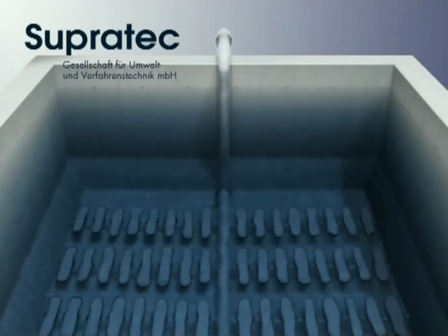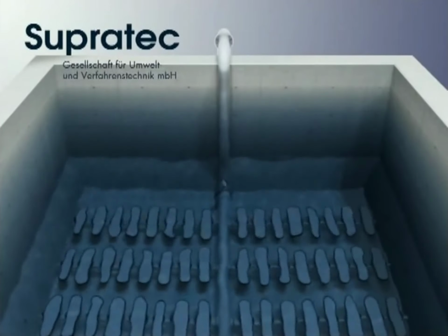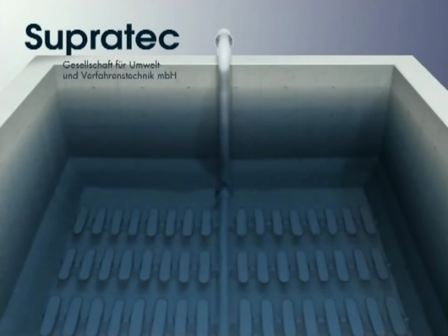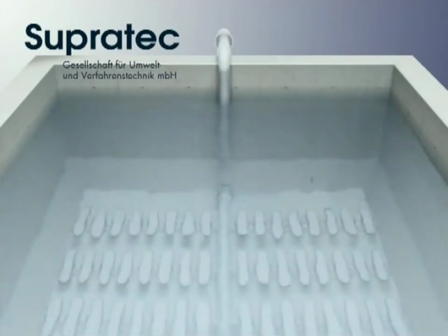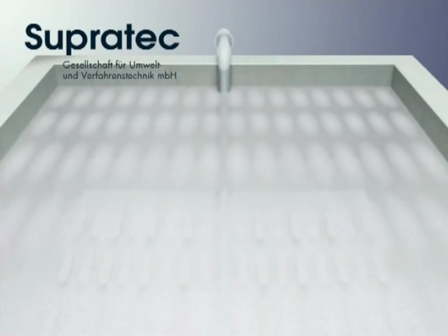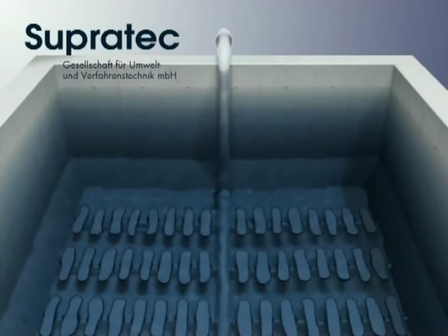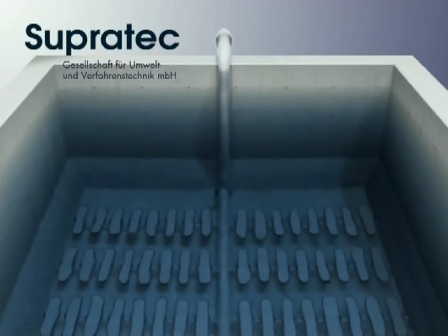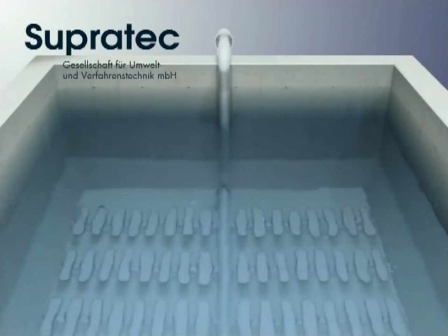If necessary, an aeration test can now be performed. All Oxyflex series diffusers and Permox series membrane diffusers can be operated intermittently. This means that the air can be shut off and remain shut off at the user's discretion. For lengthy periods of downtime, agitation devices, for example, should be used to prevent deposits from settling on the floor.